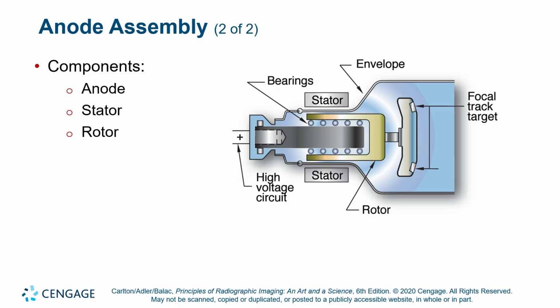Okay? Now, where does the positive charge come through? Well, the rotor axle is connected to the rectifier, and then by virtue of the ball bearings between the center axle of the rotor and the collar of the rotor, the collar is free to engage in rotational motion, but transfers the net positive charge from the anode stem through the bearings to the armature, the collar, then to the axle of the rotating anode, and then to the surface of the anode wheel, which includes the tungsten focal track.